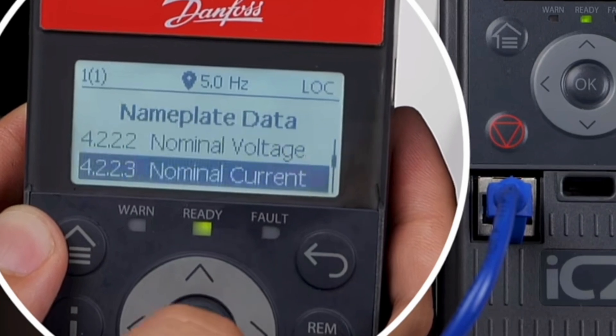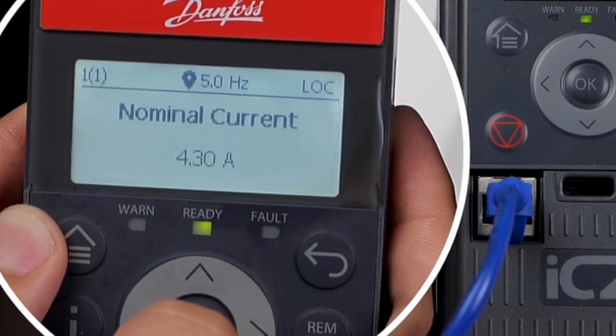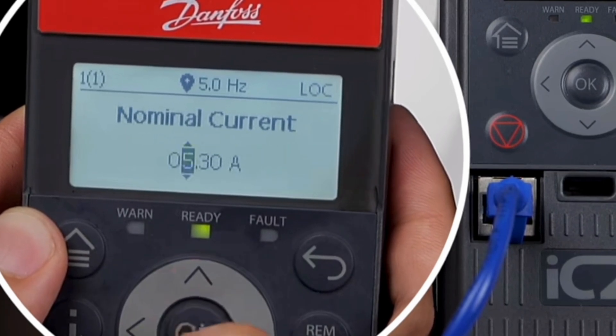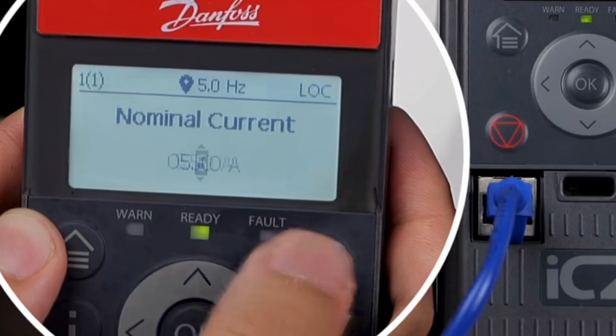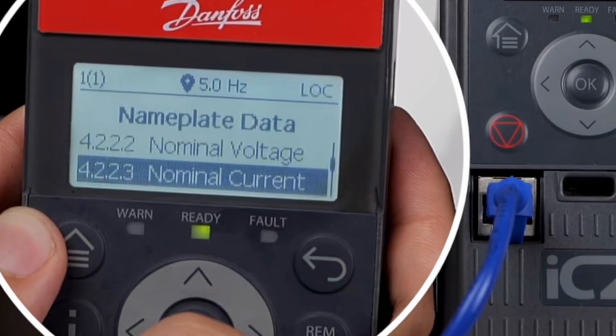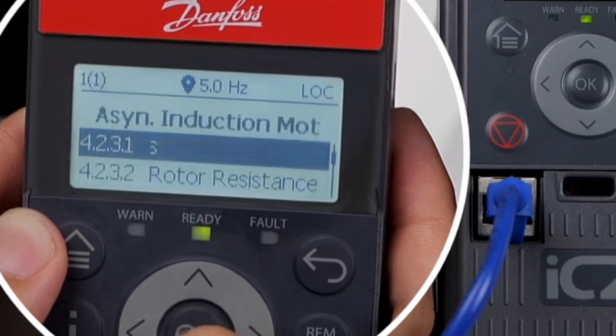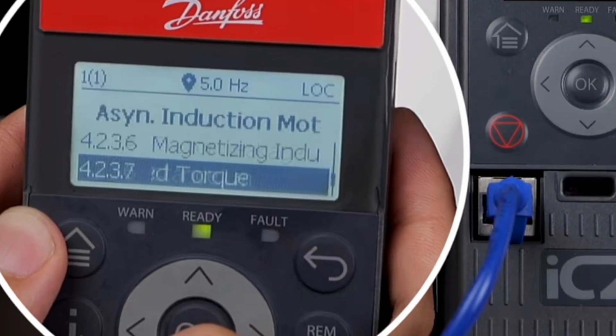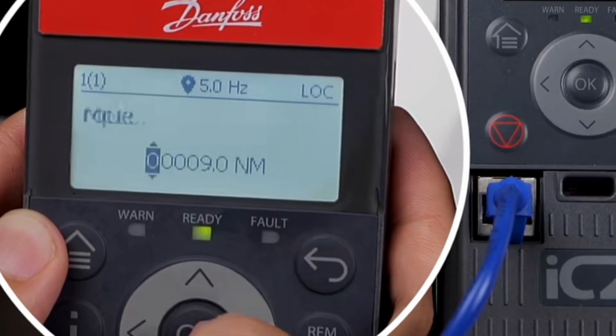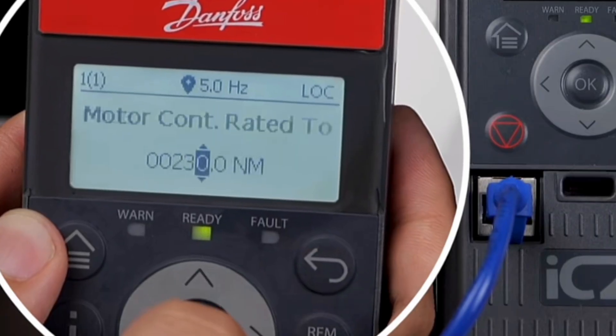Select parameter 4223 and set the nominal current to 5.50 amps. Next, select parameter 4237 and set the rated torque of the motor to 230 Nm.